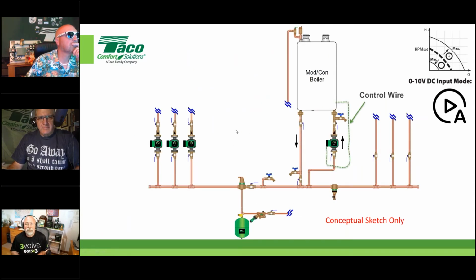I will say this, some of the boiler manufacturers out there have an external control signal that you would run a wire from the boiler to the circulator, and they control the speed of this pump based on some input that the boiler can actually see, which is a good thing, and use it to your ability. So if you have it, great, but here's the two things that have to match up. The boiler has to be able to give the signal, and the circulator has to be able to receive it. Taco has circulators that have those signals. They're typically 0 to 10 volt DC or pulse width modulation.